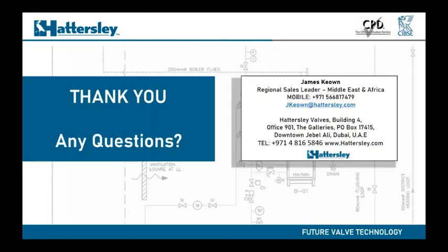Usually, I would say yes. CIBSE tend to want to see that you've got flow verifications, obviously witnessing from your client. So having a flow measurement device and being able to measure each of your fan coil units, you can tell if you've got any blocked, if you've got any problems within the system. And it just helps with commissioning and setting up of your PICVs. As I mentioned before, and as you can see from the flow charts, setting set points on, say for instance, between 2 and 4 on a 15mm low flow have more or less the same minimum activation. Your test points on your PICV will only indicate that you have between minimum activation and maximum activation.